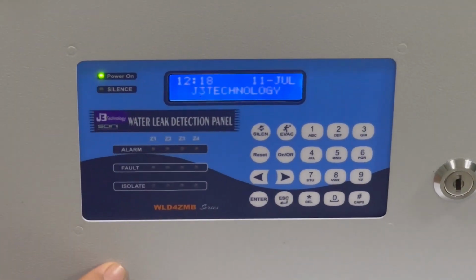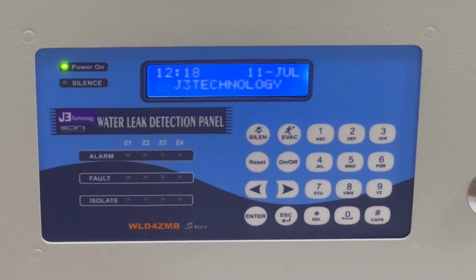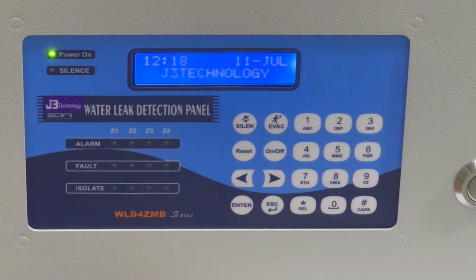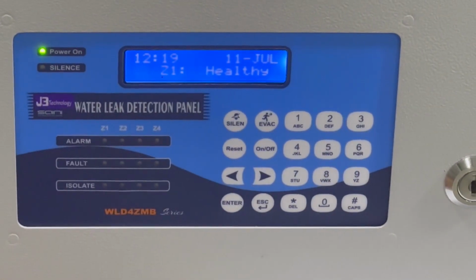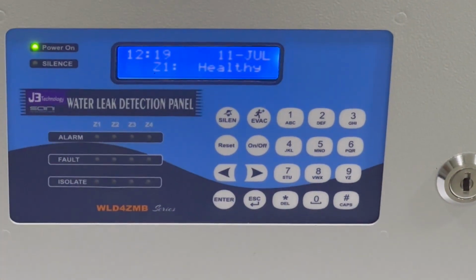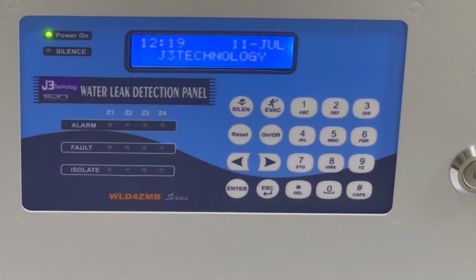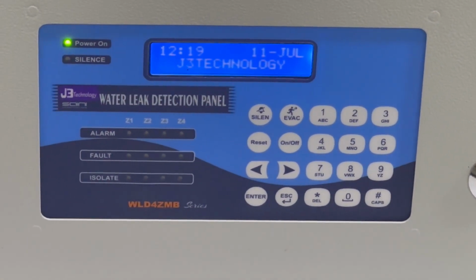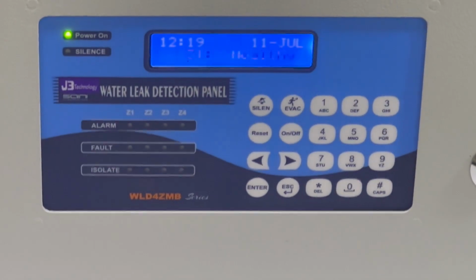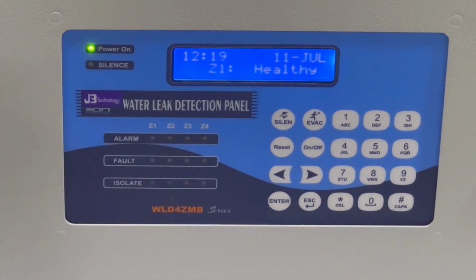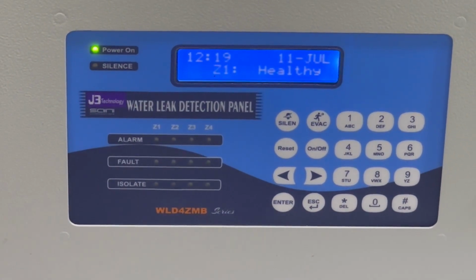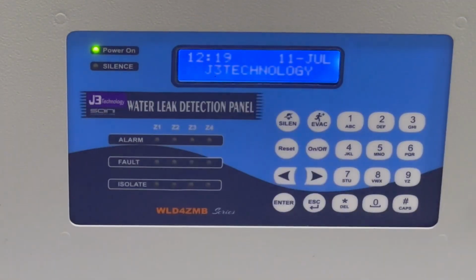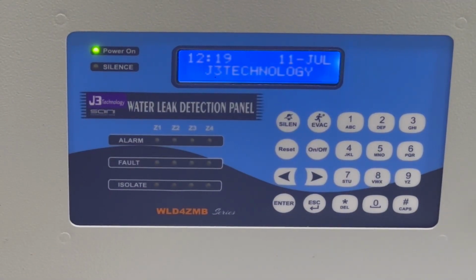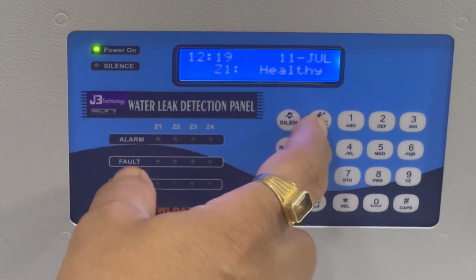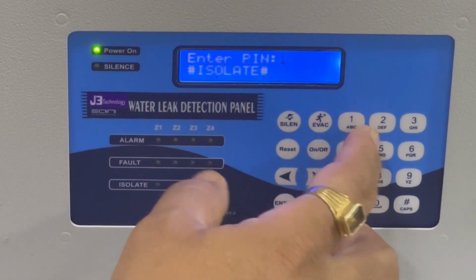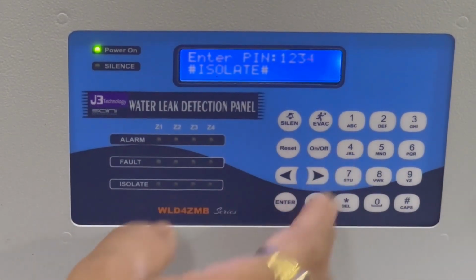Evacuate means, suppose there is zone 1, zone 2, and in zone 2 some work is going on in that premises, so there should not be a false alarm as the work is going on, some cleaning is going on. In that case you can do one more thing: you can isolate that zone, so there will be no alarm over that zone. So you have to press the evacuate button. Again it will ask for your password, 1 2 3 4, the factory default password.